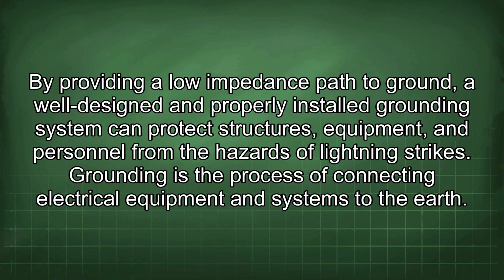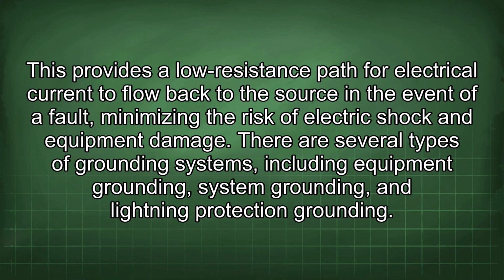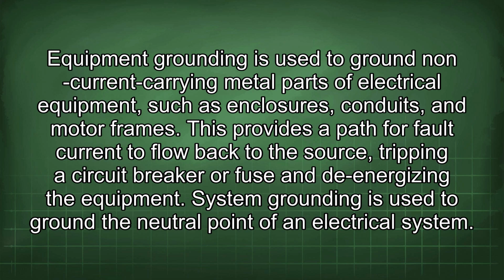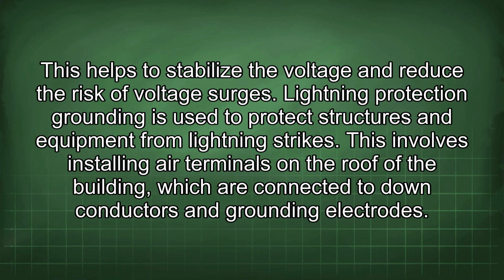Grounding is the process of connecting electrical equipment and systems to the earth. This provides a low resistance path for electrical current to flow back to the source in the event of a fault, minimizing the risk of electric shock and equipment damage. There are several types of grounding systems, including equipment grounding, system grounding, and lightning protection grounding. Equipment grounding is used to ground non-current carrying metal parts of electrical equipment, such as enclosures, conduits, and motor frames. This provides a path for fault current to flow back to the source, tripping a circuit breaker or fuse and de-energizing the equipment. System grounding is used to ground the neutral point of an electrical system. This helps to stabilize the voltage and reduce the risk of voltage surges.